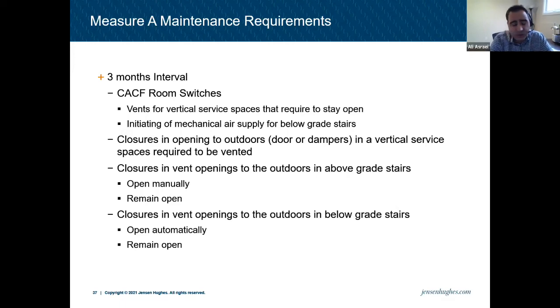CACF room switches need to be tested. Anything that you have to manually operate, you need to make sure that from the CACF room you can initiate the fans here or there and turn them on or off. And of course, automatically from the fire alarm system as well.